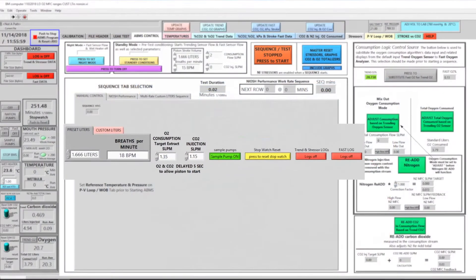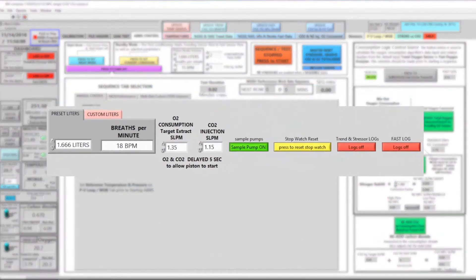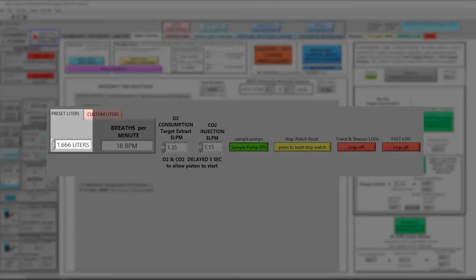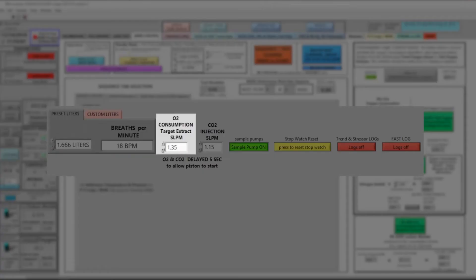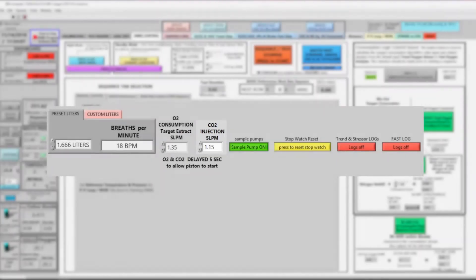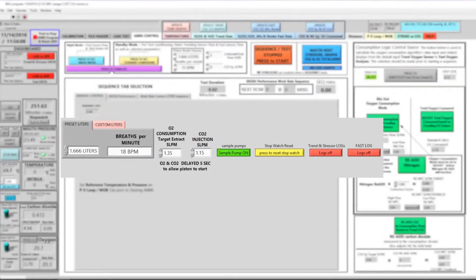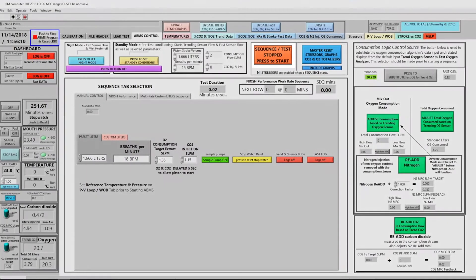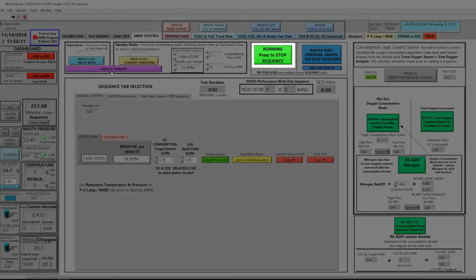Here on the control tab of the ABMS, we can set the parameters for volume, breaths per minute, oxygen consumption and CO2 injection in order to simulate a human working an extended period of time.